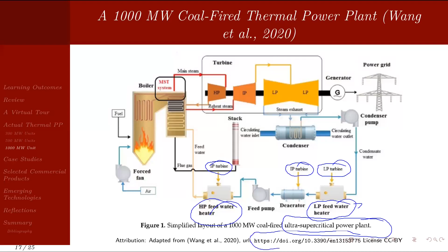For the LP feed water heater, the steam is coming from the LP turbine, low pressure turbine. For the HP feed water heater, steam is extracted from the IP turbine. For the deaerator, steam is also extracted from the IP turbine - it's written clearly here. So this is the 1000 megawatt power plant; you can get more details, but due to time constraints I cannot go into details. You can visit this link and download the article to study it.